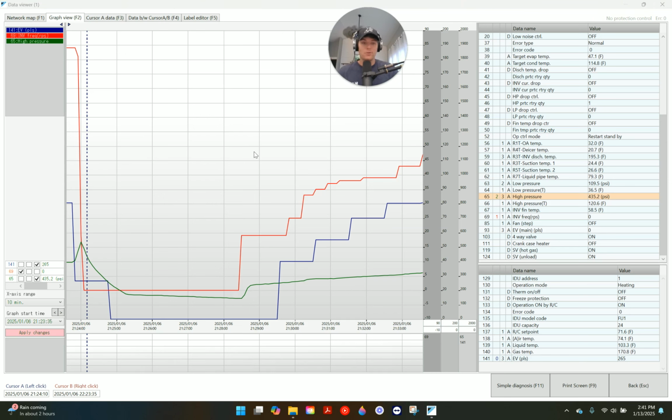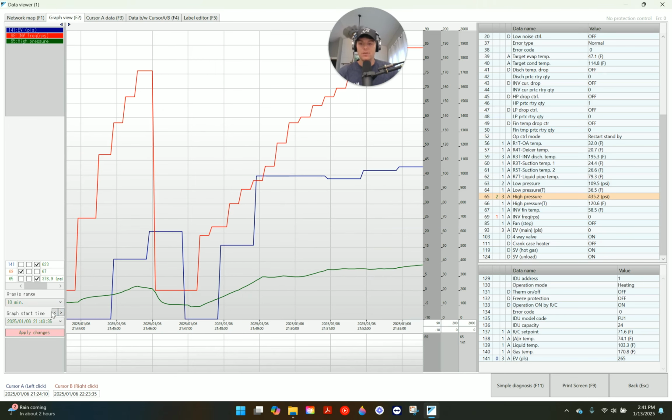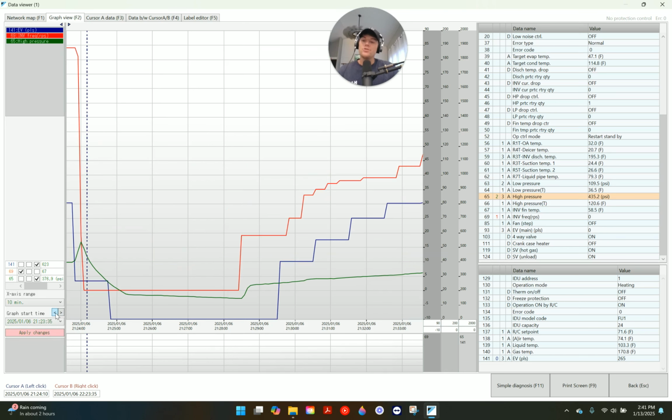Well, it went into the notorious restart standby. Restart standby says, hey, I found a problem. I don't know what it is. I'm going to restart. And it restarts and it starts to operate again. And wouldn't you know, you don't have an issue anymore. There isn't any more trips. There isn't any more times where the system actually has an issue, and I can actually zoom out and look at that. But that goes to show me that on this particular set of data, what would cause a trip like this is overcharge, right?